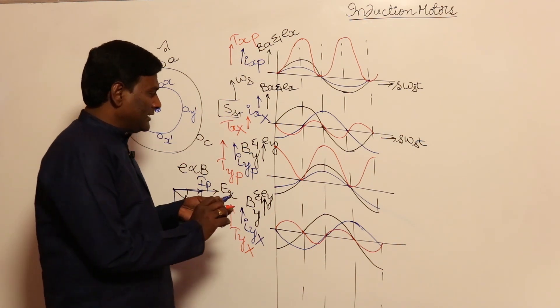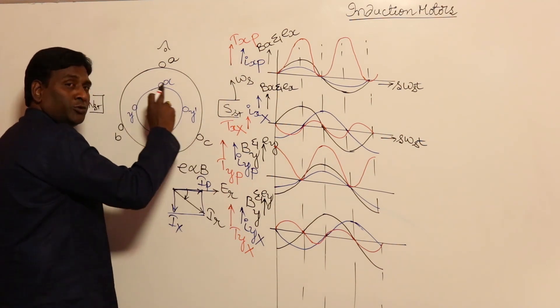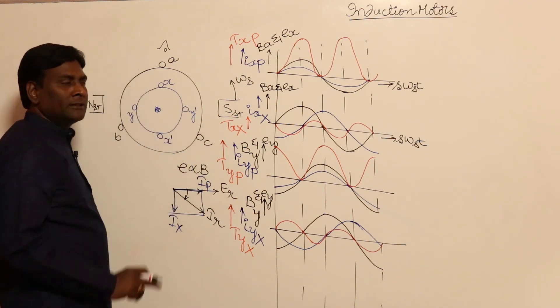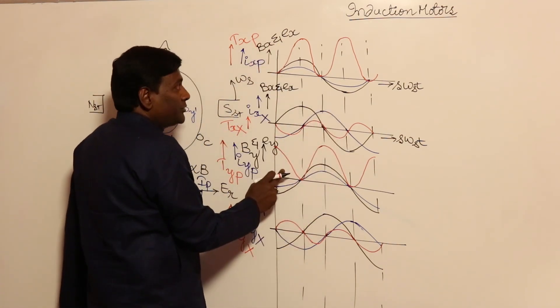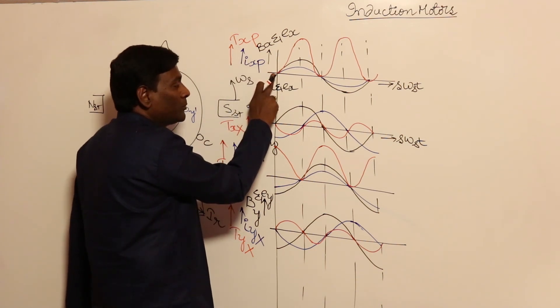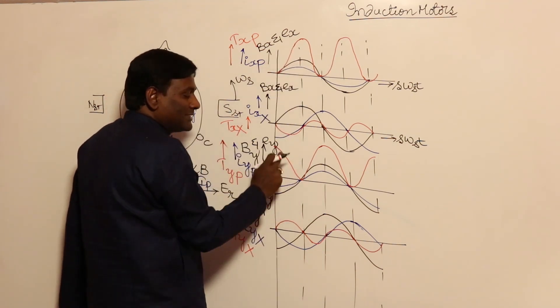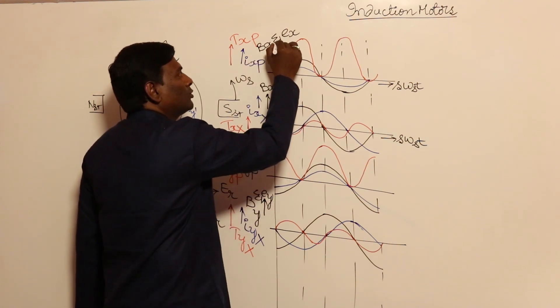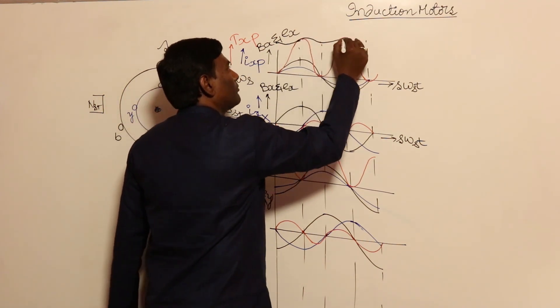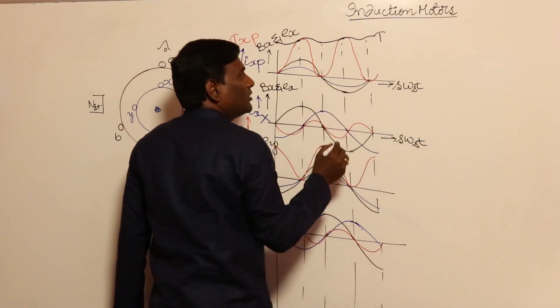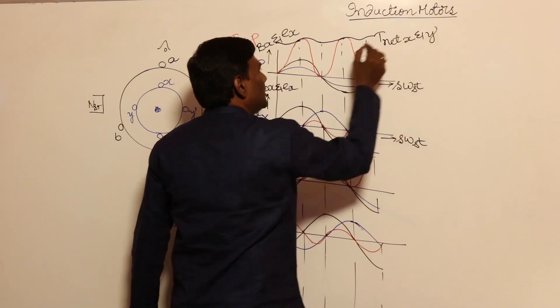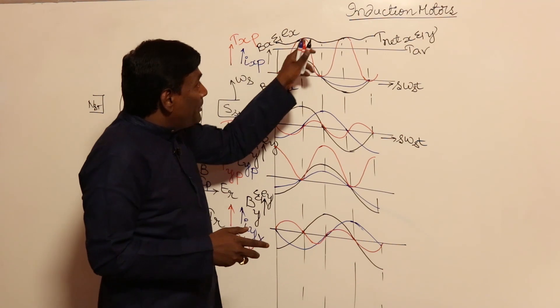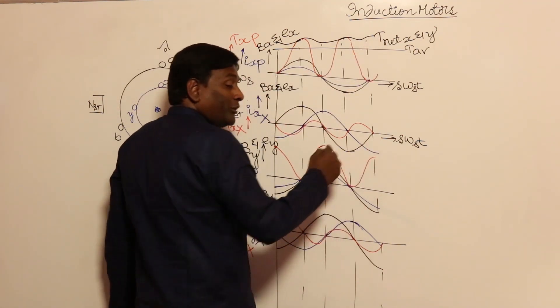Let us observe. If I combine, the net torque produced is because of X, X dash torque produced plus Y, Y dash torque produced, giving the net torque developed in the rotor. Looking at the in-phase components: whenever the torque from X is 0, the torque from Y is maximum. Whenever torque from Y is 0, torque from X is positive maximum. So this plus this — the net torque developed because of X, X dash and Y, Y dash — average torque production is improved, and pulsations are reduced.